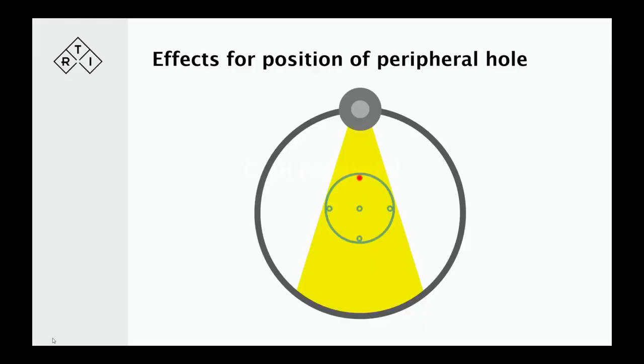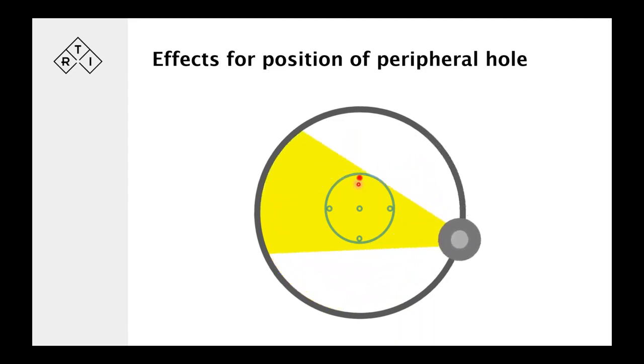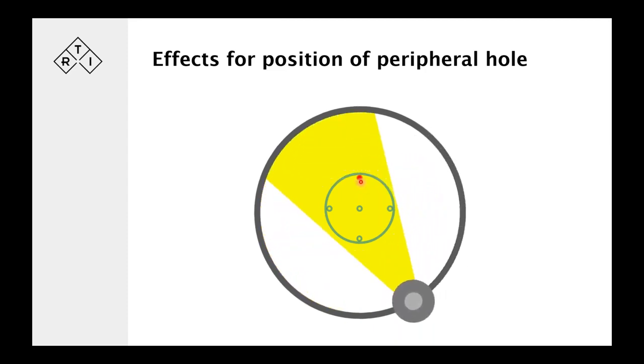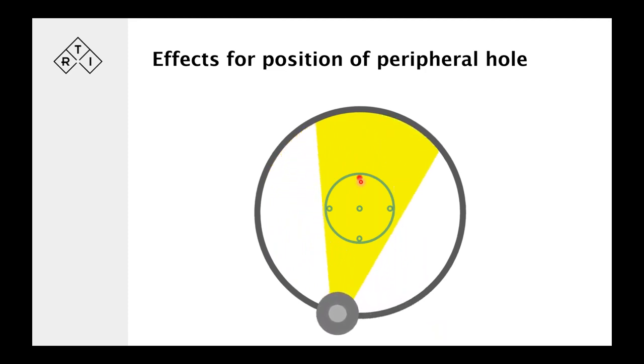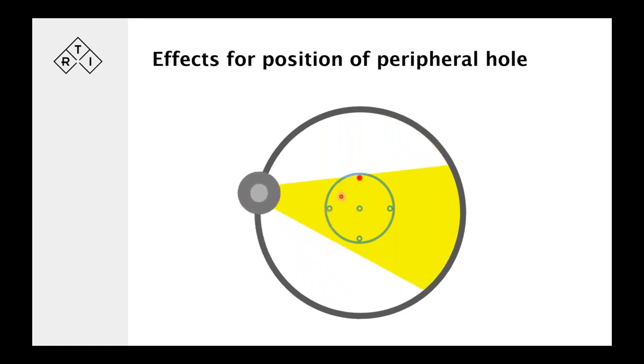Another thing we found was that we had an effect also when measuring the CTDI in the peripheral holes, gathering data for the weighted CTDI. And of course, measuring in the peripheral holes is what we want to do. What happens when we do is that the distance from the tube itself changes, so the dose rate will change due to the distance, for one, but also due to the added attenuation and scatter generated inside the phantom.